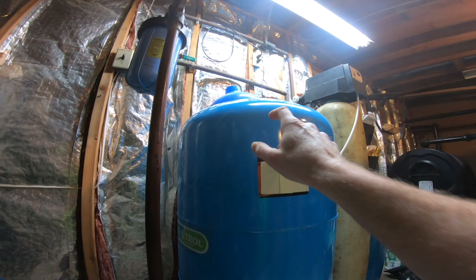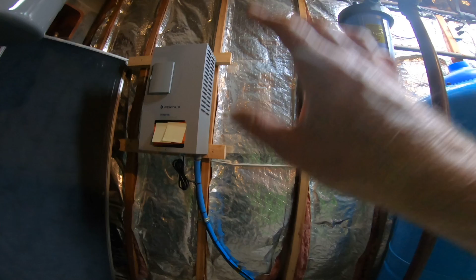When you set this up, you're supposed to take the pressure. You know, when you set a pressure tank, it's supposed to be pressurized to 2 pounds below the low cut in. So with this, it's supposed to be 70% of what you set this to. So I asked the guys to set it to 60 psi. So it should have been set at 70% of 60, which is okay.